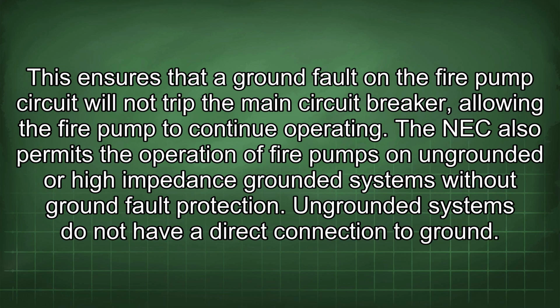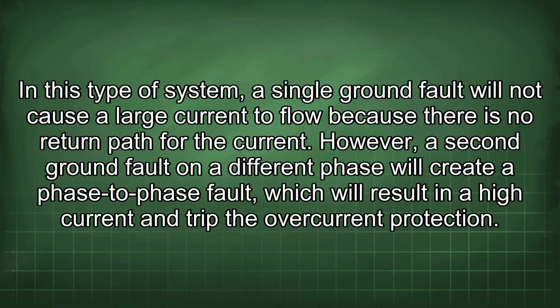The NEC also permits the operation of fire pumps on ungrounded or high impedance grounded systems without ground fault protection. Ungrounded systems do not have a direct connection to ground. In this type of system, a single ground fault will not cause a large current to flow because there is no return path for the current. However, a second ground fault on a different phase will create a phase-to-phase fault, which will result in a high current and trip the overcurrent protection.